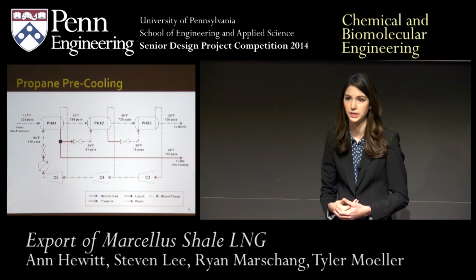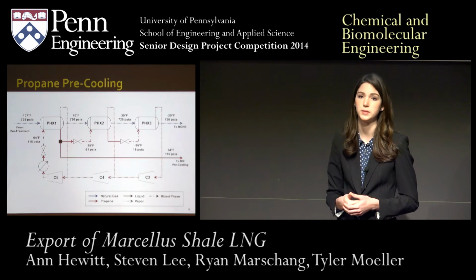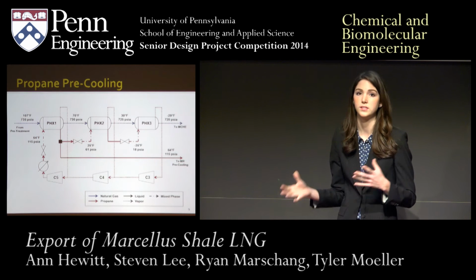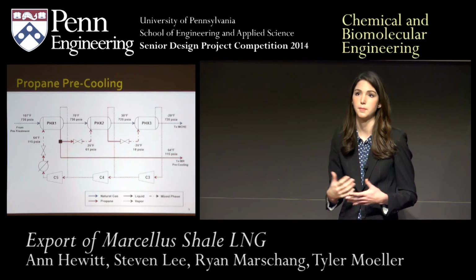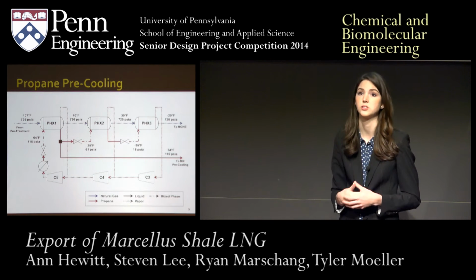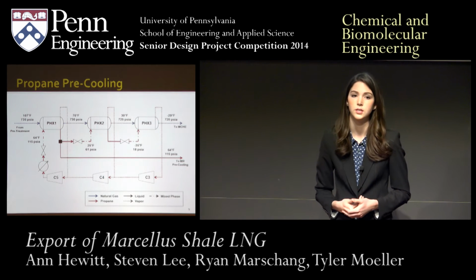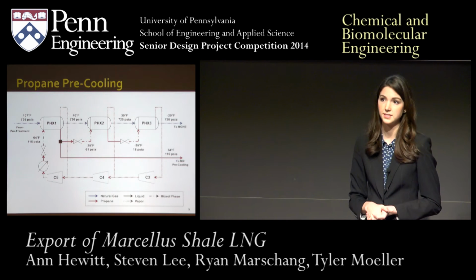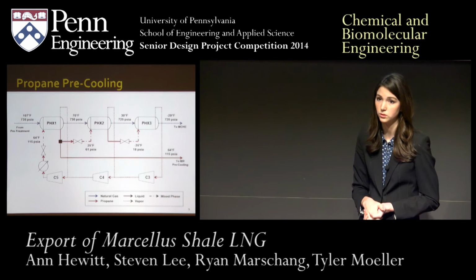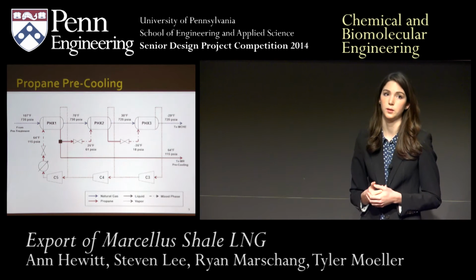In designing these heat exchangers, we first looked at using one heat exchanger as the most capital efficient solution, but found that using three heat exchangers was the most thermodynamically efficient, optimizing and minimizing our overall operating costs. We also wanted to get as much cooling capacity out of our propane refrigerant as possible, and our choice of heat exchanger really helped with this.